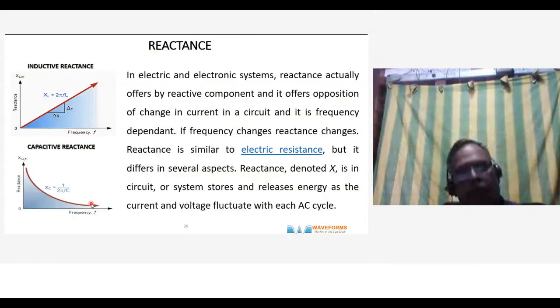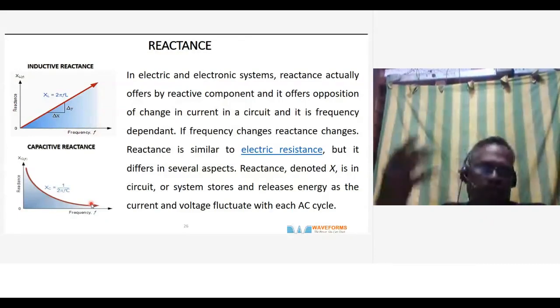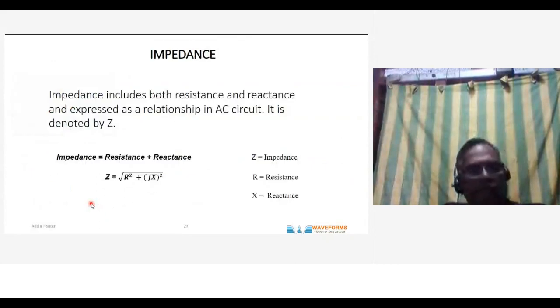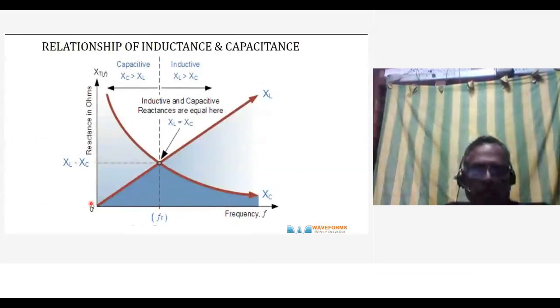We use this technique because when inductive and capacitive reactance intersect at some point, I'll come to impedance. This is the important relationship of inductance and capacitance. At a particular frequency, say the fifth harmonic, if XL is equal to XC, they resonate at that frequency. This is called resonance. When you have the inductance of the system and the capacitor, the frequencies interact with the network and cause resonance.